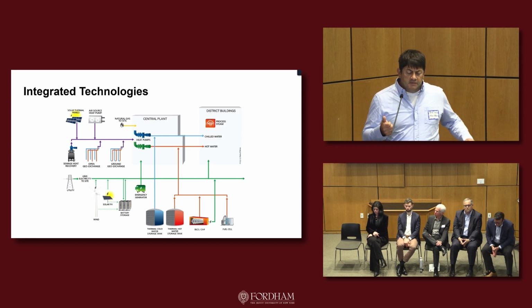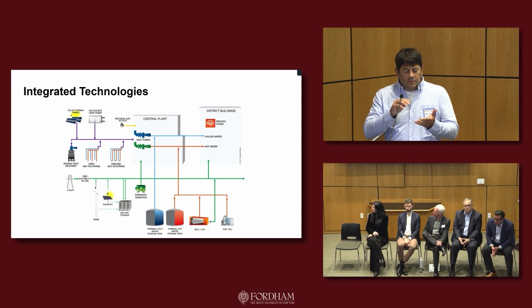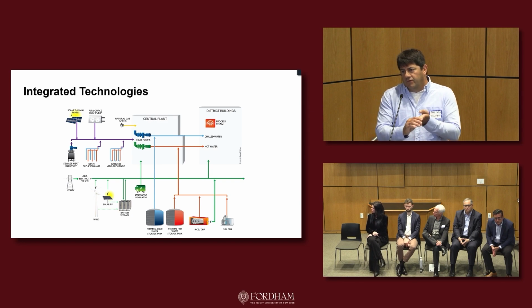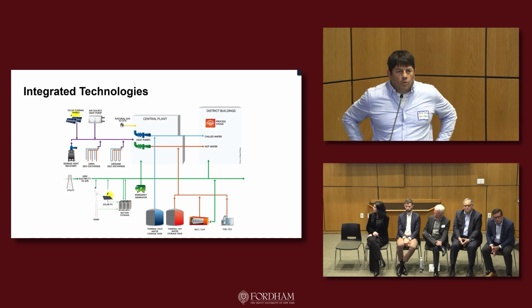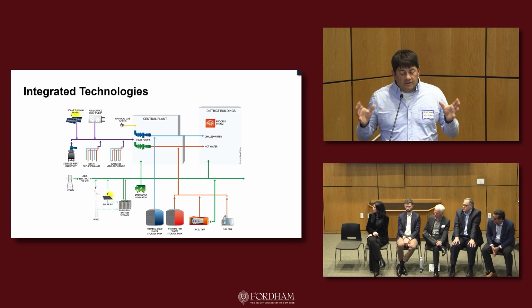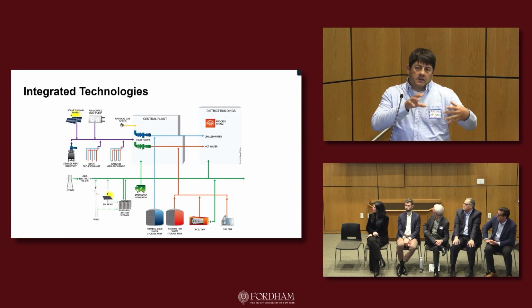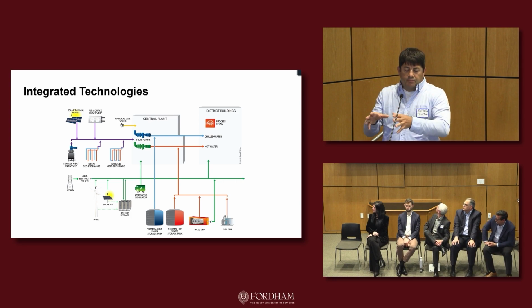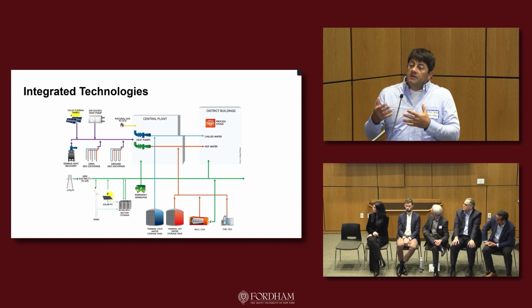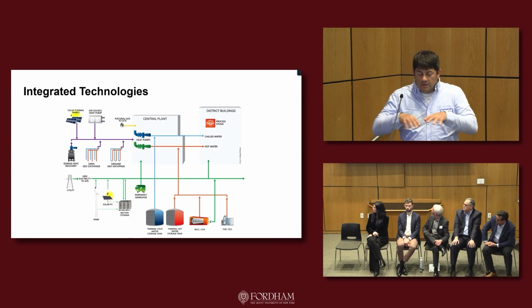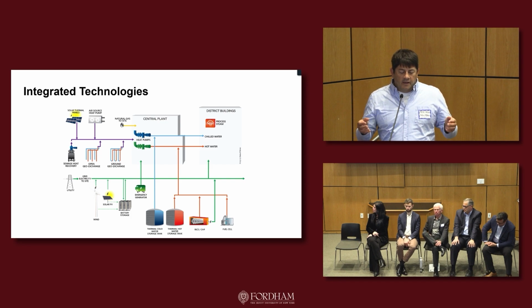A couple big things you're seeing a lot of are ground source, air source, sewage heat recovery, and air side energy recovery in buildings—those are really the 4 energy sources we've been dealing with a lot. But then how do you take those energy sources, apply a heat pump, and implement some type of thermal storage? Because it all has to work together and be sized properly.